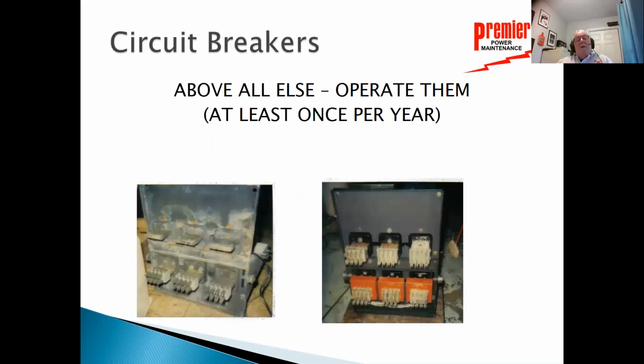Okay, with just the few minutes we have left, I want to talk a little bit about circuit breakers and a little bit about cables. We'll keep it very brief. Circuit breakers, above everything else, operate the circuit breaker at least once a year. The biggest problem with circuit breakers is they don't get operated, and when they need to operate, they don't operate in the same manner that we expected them to.